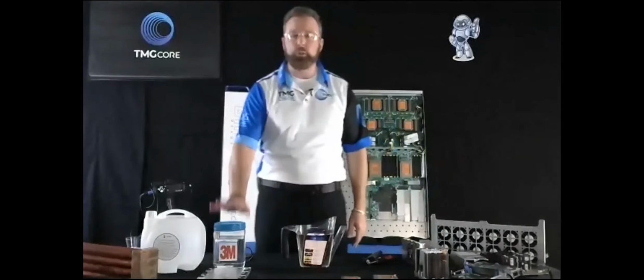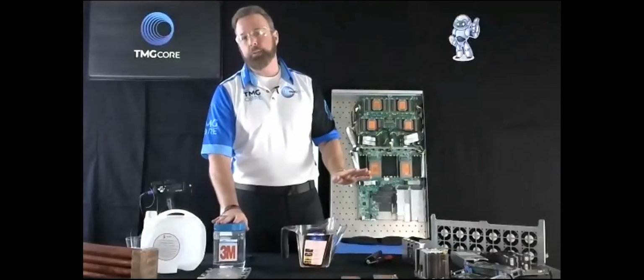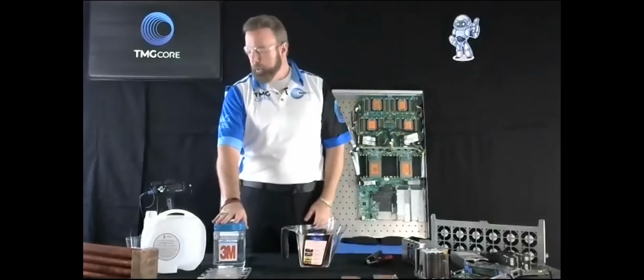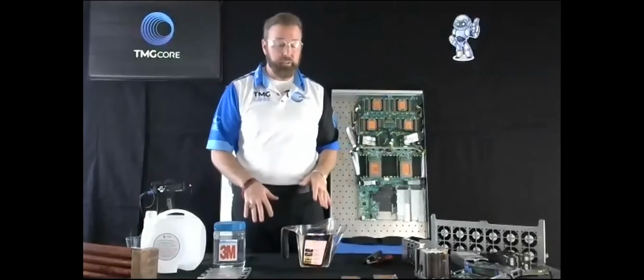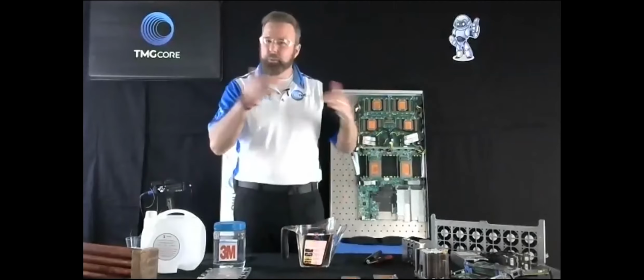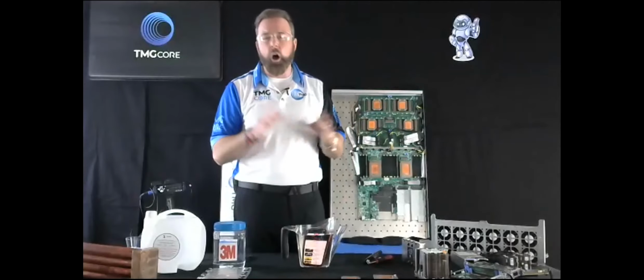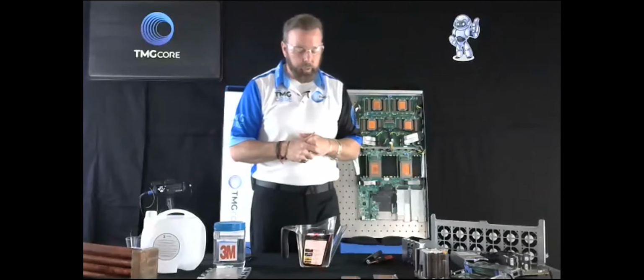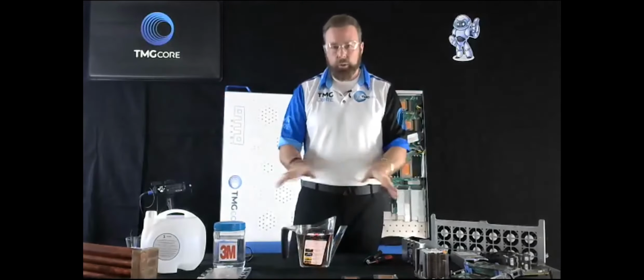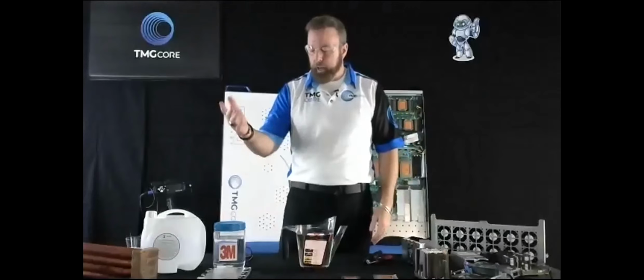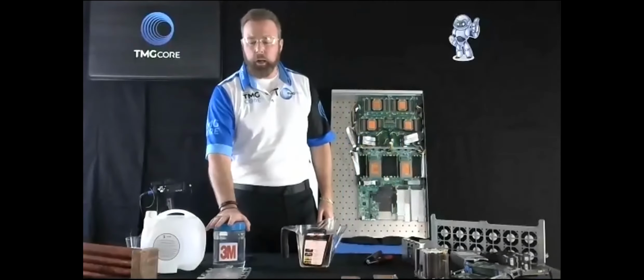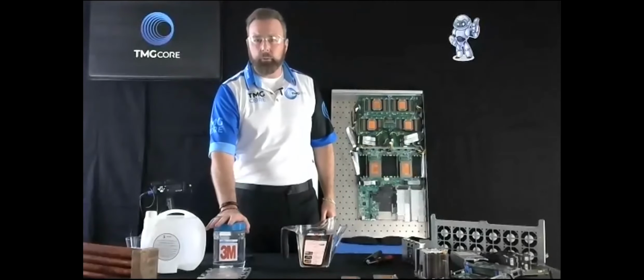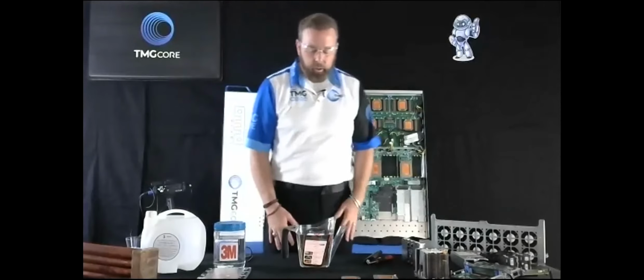In some cases, they use this to put fires out, since it has no flash point, and again, very inert. Whereas minerals and similar single-phase fluids have flash points, and you typically need some secondary fire suppression systems, not always, but with this stuff it's just not necessary. In fact, I think 3M makes a great Novec fire product that's very similar to this in nature.